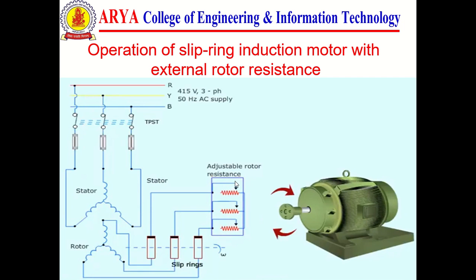What is the importance of external rotor resistance? With the help of this external resistance, the rotor resistance can be increased or decreased. At the time of starting, this value is kept as high as possible so that there is minimum flow of current in the rotor winding, as well as minimum stator current.